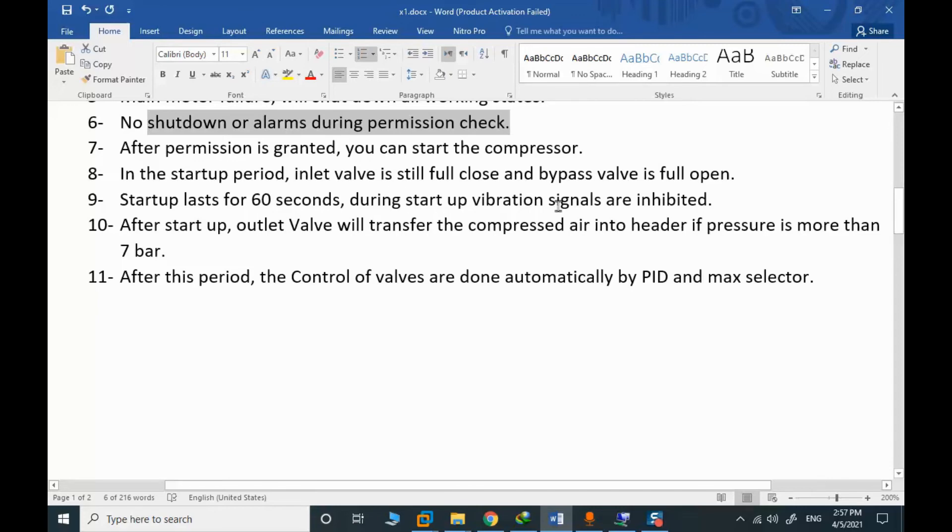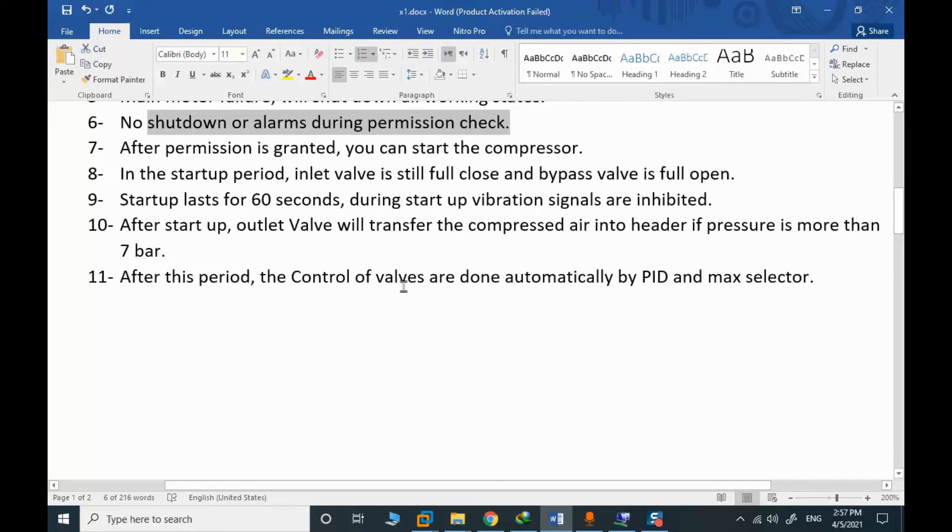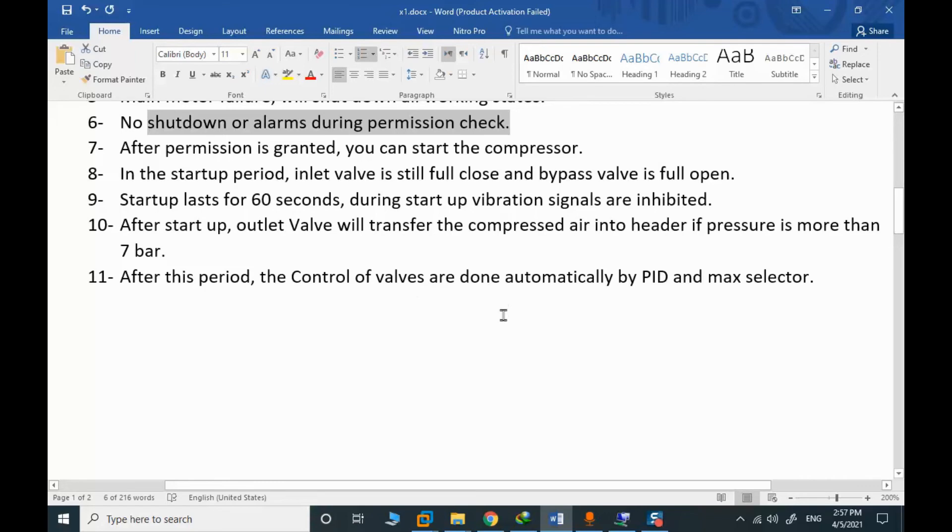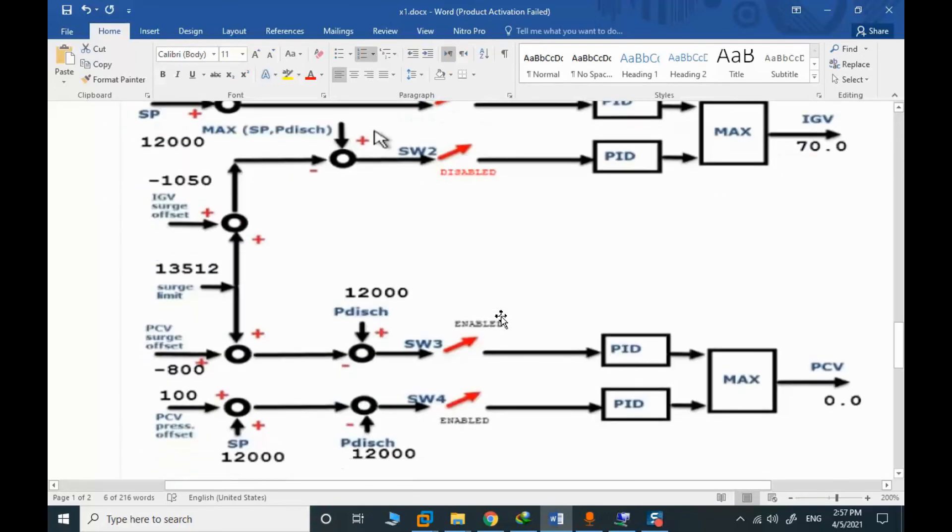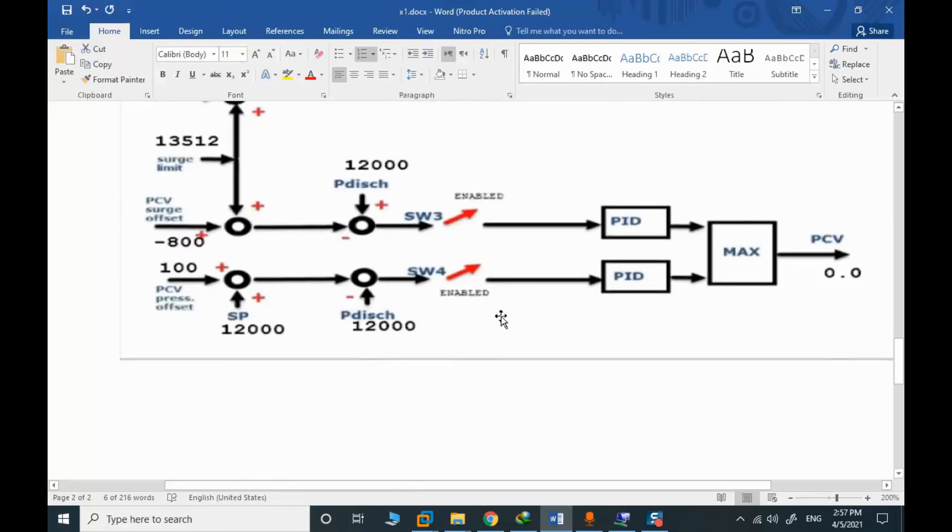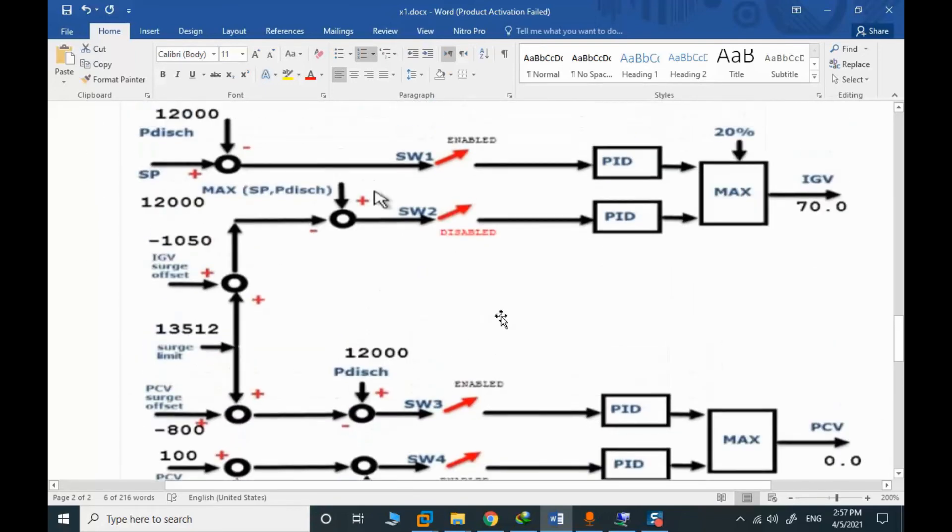During the startup, vibration signals are inhibited. After startup, outlet valve will transfer the compressed air into the header if the pressure is more than 7 bar. After this period, the control of valves are done by PID max selector. That is this structure.